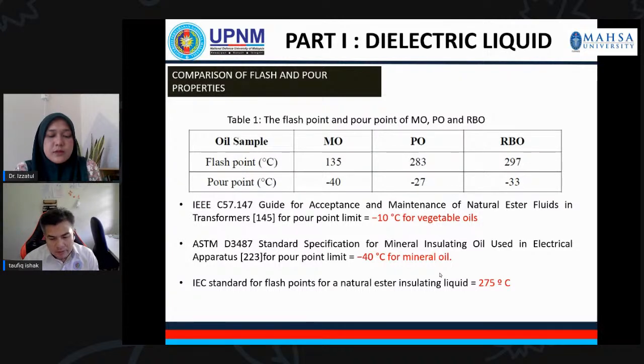However, based on the standard ASTM D3487 specified for mineral oil, the pour point limit is minus 40 degrees C, which is good for mineral oil. And for vegetable oil, it is based on IEEE C57.147. For natural ester, they recommend that the pour point for vegetable oil must comply at minimum with minus 10 degrees C. And in our case, we already surpassed the minimum value, with negative 27 and negative 33, which is very good for application inside the transformer.